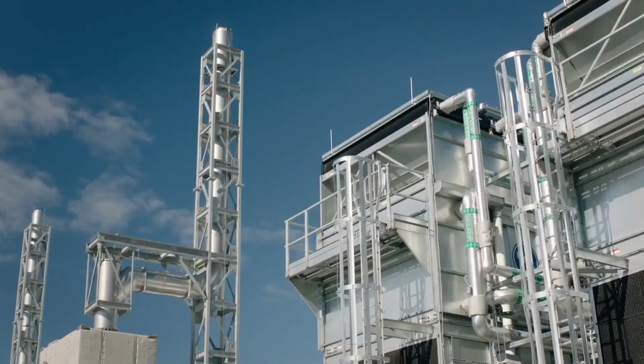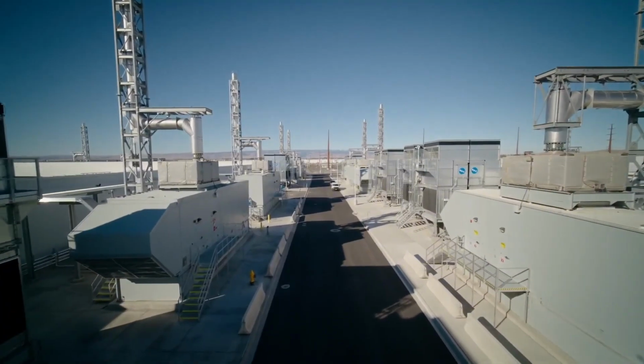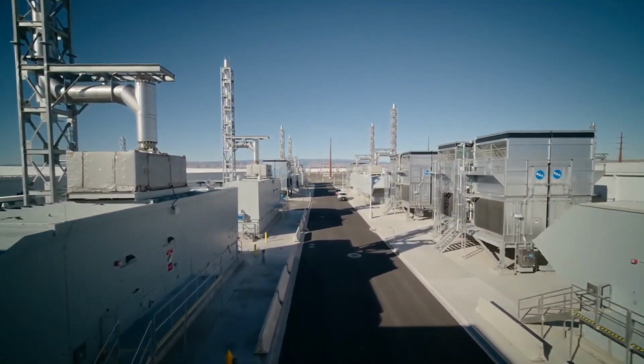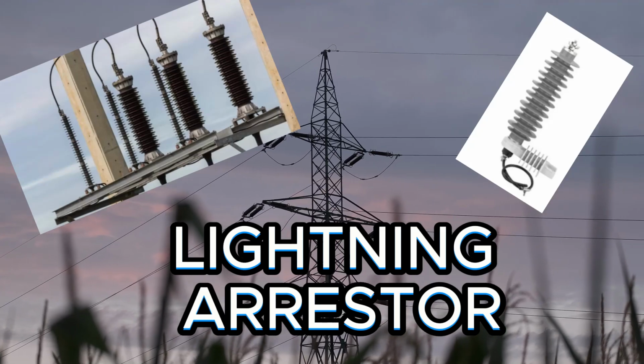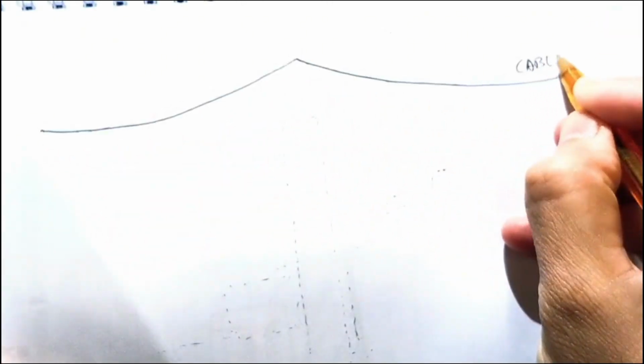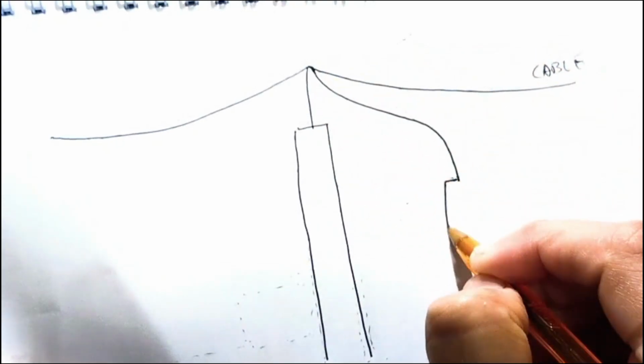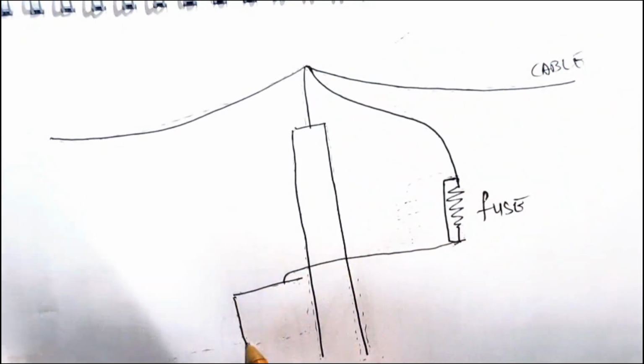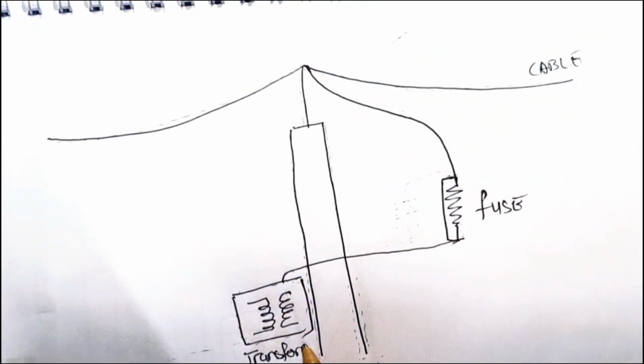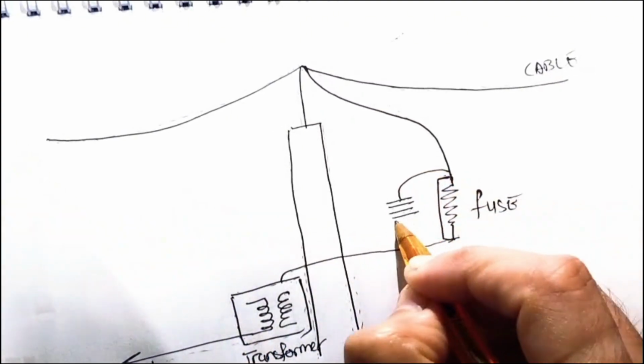But what exactly tripped the entire system and all these 60 data centers hit the panic button? Get ready because this part is wild. It's because of this lightning arrestor. And at 7 p.m. on July 10, 2024, a lightning arrestor did fail on a 230 kilovolt transmission line in Eastern Interconnection. That kicked off a permanent fault and locked out the transmission line.